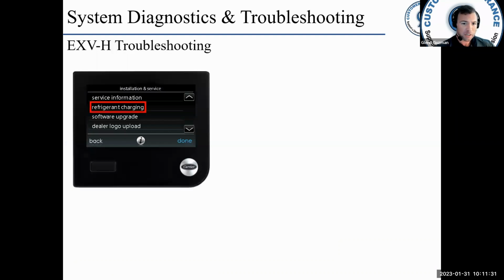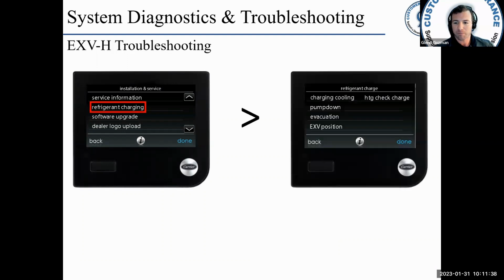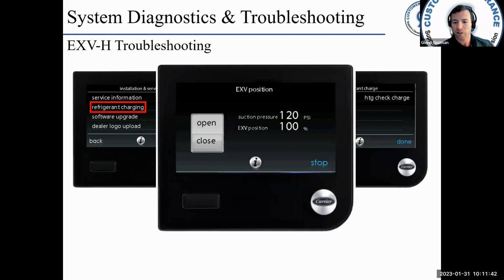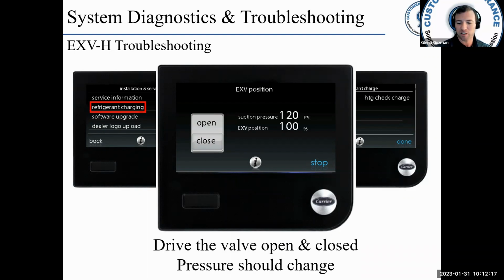So, EXV troubleshooting. Another way you can troubleshoot this valve: go into refrigerant charging in the advanced menu, go to EXV position and take a look at it. Hey, I've got EXV position, open and close. You see the suction pressure, you see the EXV position. You can actually drive this open and closed, and you should see a corresponding suction pressure change. It depends on exactly when you do this. If the unit is, say, in standby mode and pressures are equalized, you're probably not going to see too much pressure differential. So it really depends on when and how you do this. But you can physically drive the valve open and close. You should see some pressure change.